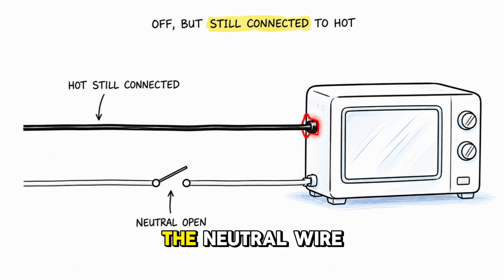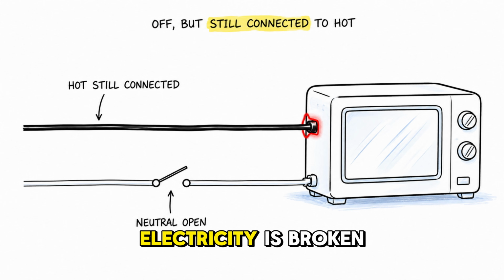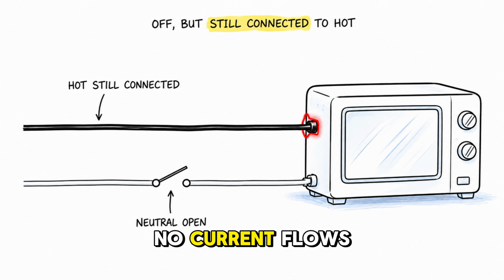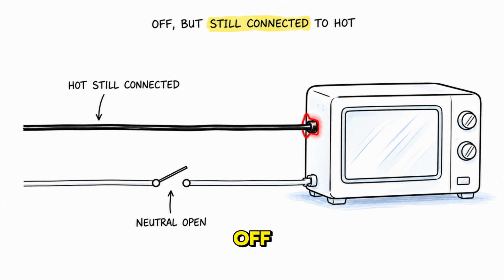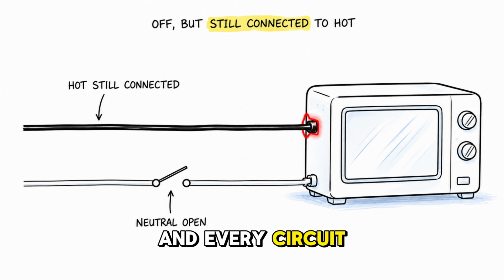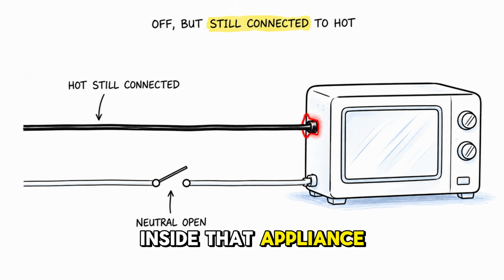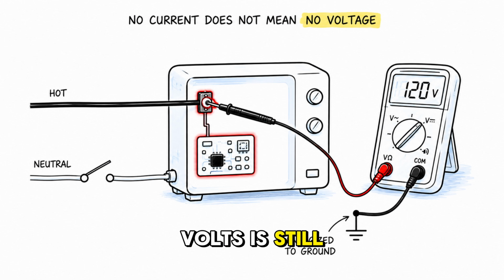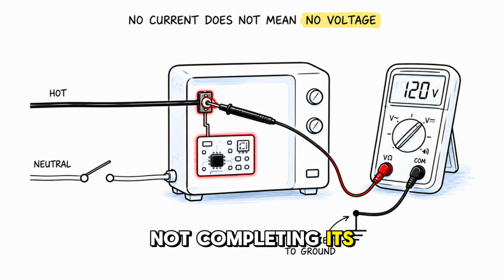When you open a switch in the neutral wire, the return path for the electricity is broken. No current flows. The appliance stops working and it appears to be turned off. However, the live wire is still connected to every internal component, every terminal, and every circuit board inside that appliance. The full 120 volts is still present on everything inside the device. The device is fully energized. It is simply not completing its circuit.